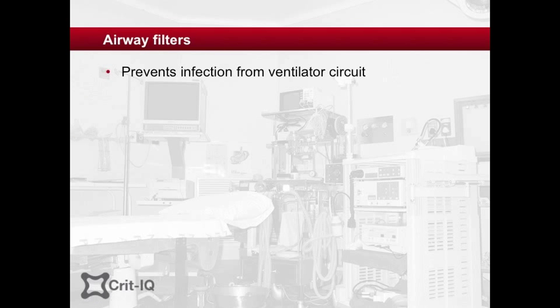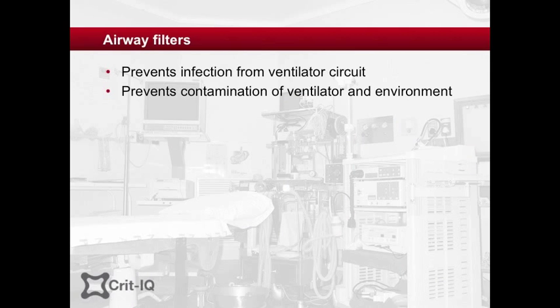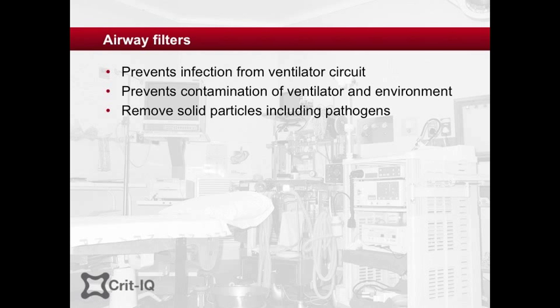The potential for ventilator-associated pneumonia to be transmitted to the patient via the ventilator circuit has led to the development of bacterial and viral filters. These disposable filters have also been used to prevent contamination of the ventilator and of the surrounding environment through the gas of the return limb in the circuit. If used correctly, many filter manufacturers quote rates of removal of more than 99% of pathogens. Filters contain material that effectively removes solid particles such as pathogens while allowing the relatively unimpeded flow of gas.